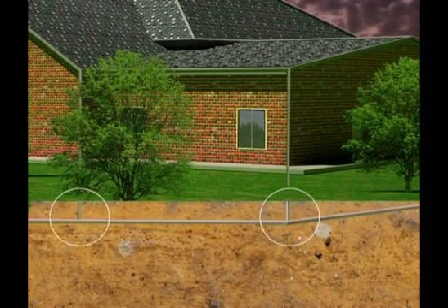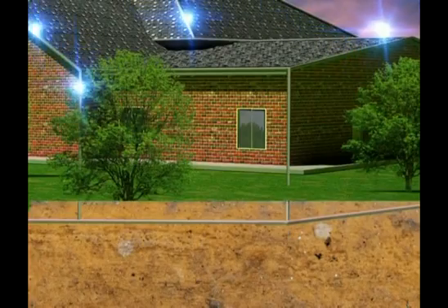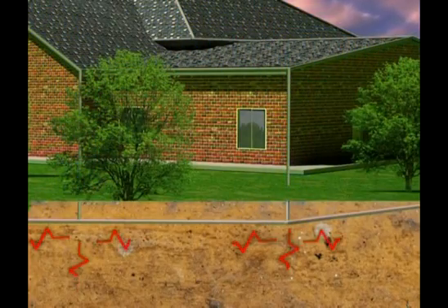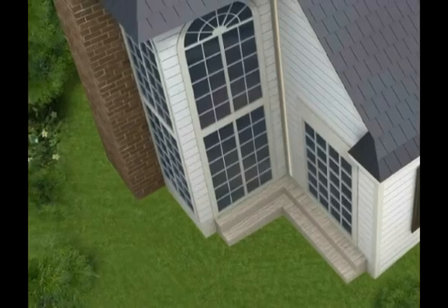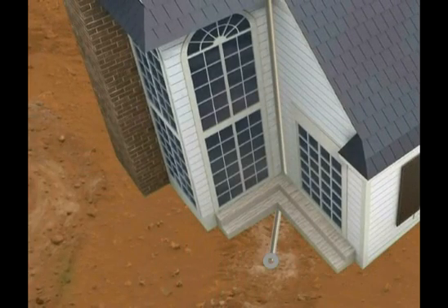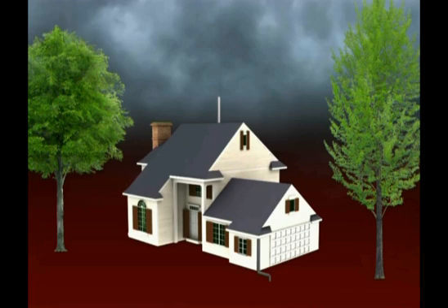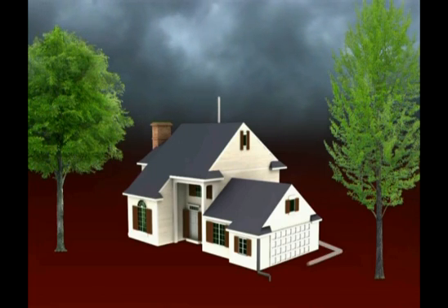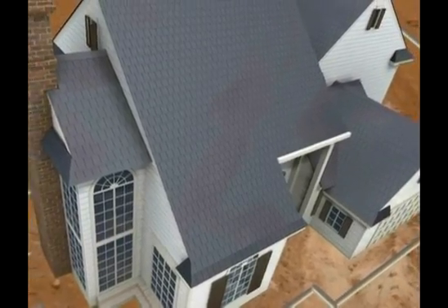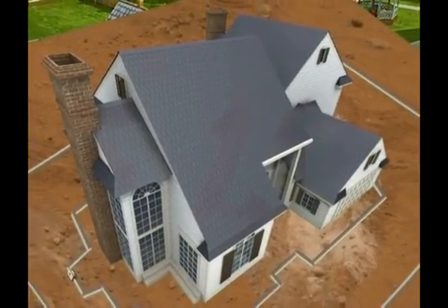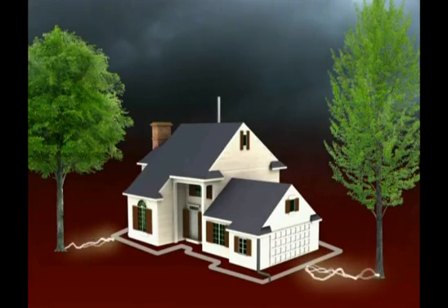The earthing system is the third component in the external protection system. It carries the electricity captured by the air terminal and conveyed by the down conductor to the earth. GI metal sheets or copper wires are used for preparing the earthing system. The earthing system is placed at a distance of one meter from the periphery of the building and at a depth of half a meter. It is always ideal to set up ring conductors around the building instead of multiple systems. In highly populated areas, it is better to install multiple ring conductors to prevent the dangers caused by step voltage, and this is also the most effective system for residential buildings surrounded by trees.